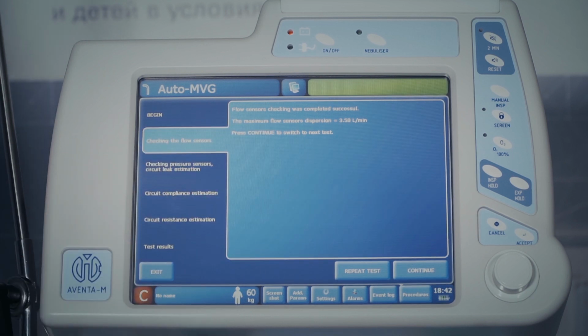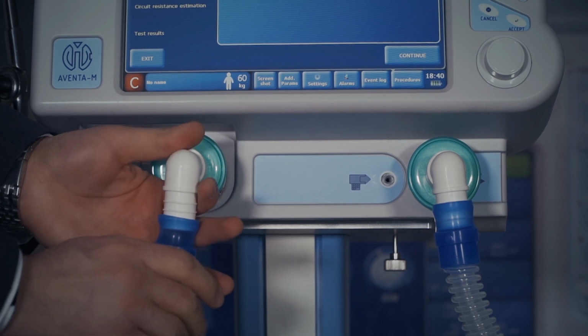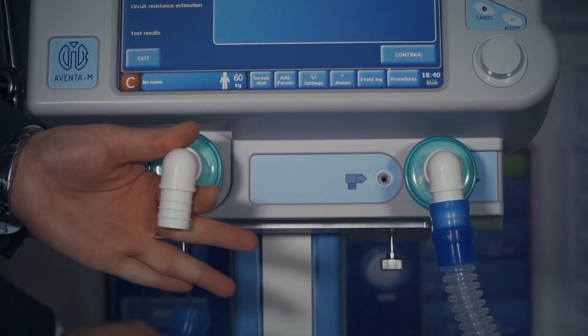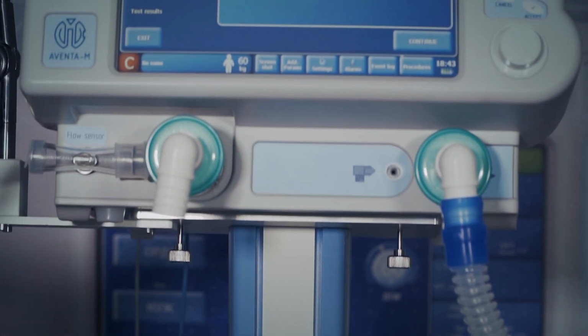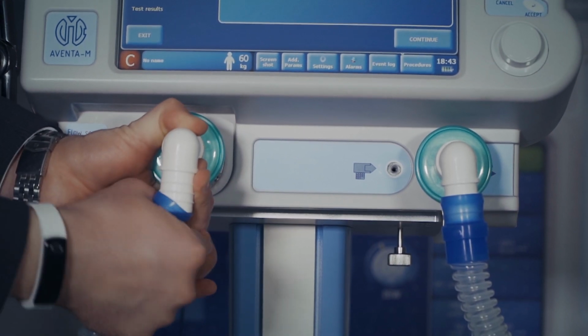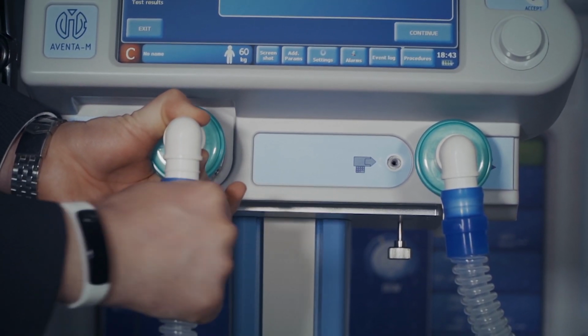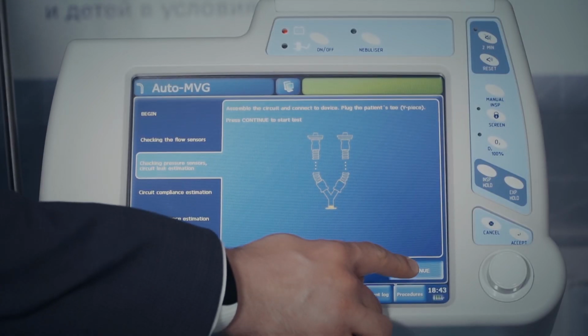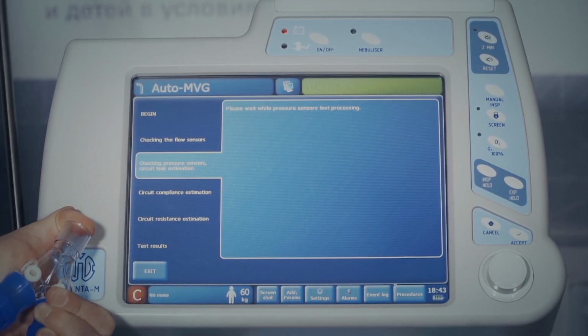The test result is displayed on the screen. To proceed to the next test, press Continue. In case of an error, follow the on-screen instructions. Prior to proceeding to leak test and pressure sensors calibration, assemble breathing circuit as shown on the screen.